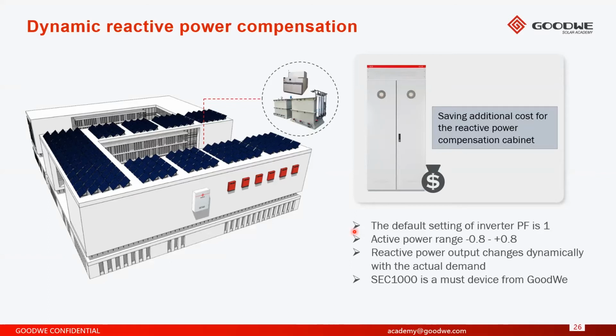In terms of the power factor range, we have a minus 0.8 to plus 0.8 leading and lagging power factor capability. By having reactive power compensation inside the inverter itself, it eliminates the need for this industrial customer to install a dedicated power factor correction unit, which traditionally does the power factor improvement on site. So with this type of solution, you have the benefits of the PV plant not only improving your power factor, but also generating electricity from the PV panels and reducing the overall on-site consumption of the industrial customer.